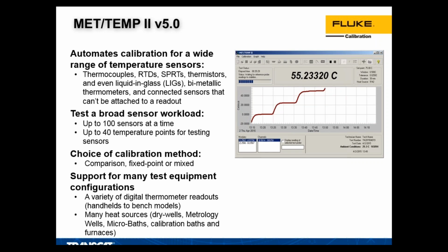You can use this program for thermocouples, RTDs, and SPRTs, but for doing SPRTs you need to be a little careful, depending on how particular you want to be about the RTPW values. Some people, when doing ITS-90 calibrations, want to collect the triple point of water after every temperature point. This program will use an average RTPW value.